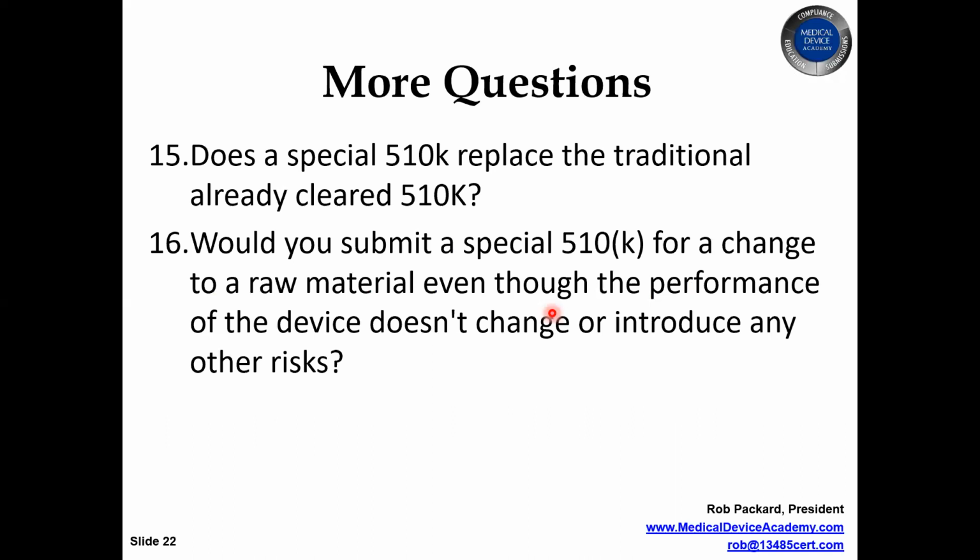So your new 510K, the new special, will list the previous one as the predicate, and both will be in the same product classification. Your old one doesn't disappear. It's just that both are in the database now. So I think that answers that question.